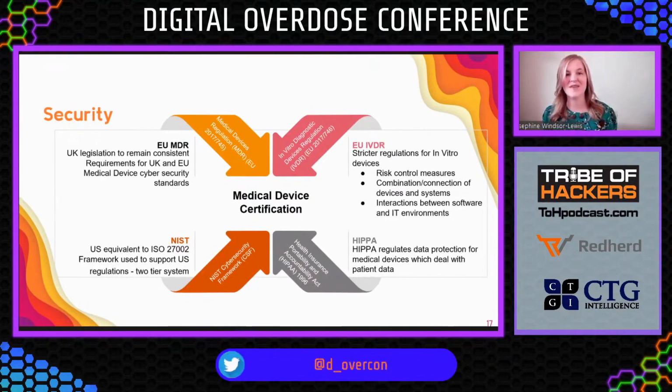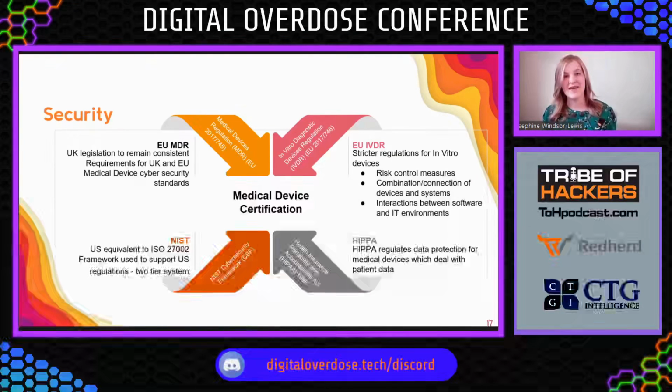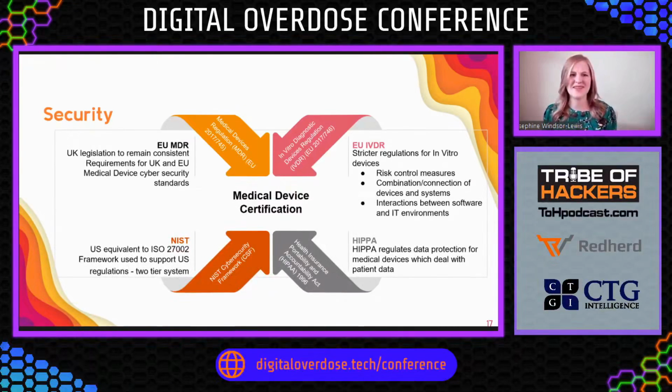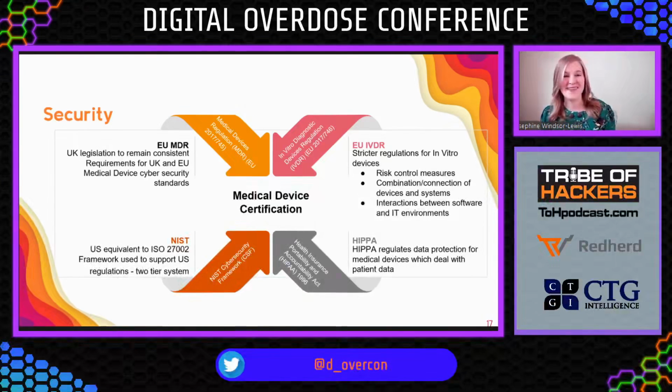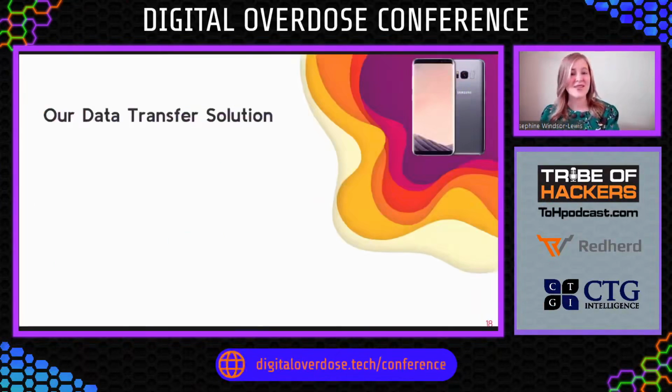We looked at all of the different certification standards around the world, and we found that the EU and UK procedures, which are still fairly similar, Brexit notwithstanding, are the strictest, right? So if you pass this certification, a lot of different countries will give you a head start in passing theirs. For example, in Ghana, you get to skip the first couple of steps in the certification process if you're already EU certified. Now, there are a lot of different specs for what a medical device has to go through to pass this certification in terms of accuracy, in terms of provable testing, but cybersecurity is a major component, especially for software. And we are just not passing those specs at the moment.